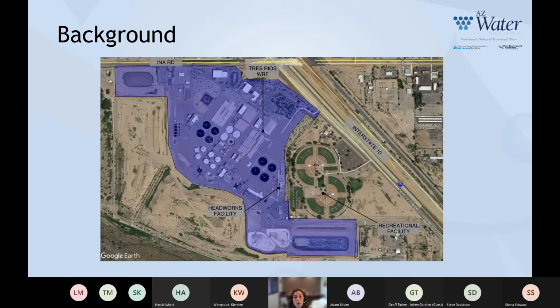So back in 2017, Pima County WRD requested that Brown and Caldwell perform an evaluation of the existing headworks, odor control, and ventilation system at the Tres Rios plant, which is located off of I-10 and the Ina Road exit just north of Tucson. The headworks, highlighted in yellow, is located adjacent to a sports complex and dirt track. Numerous odor complaints were received from the nearby facility, and occasional attention was garnered from local media outlets.